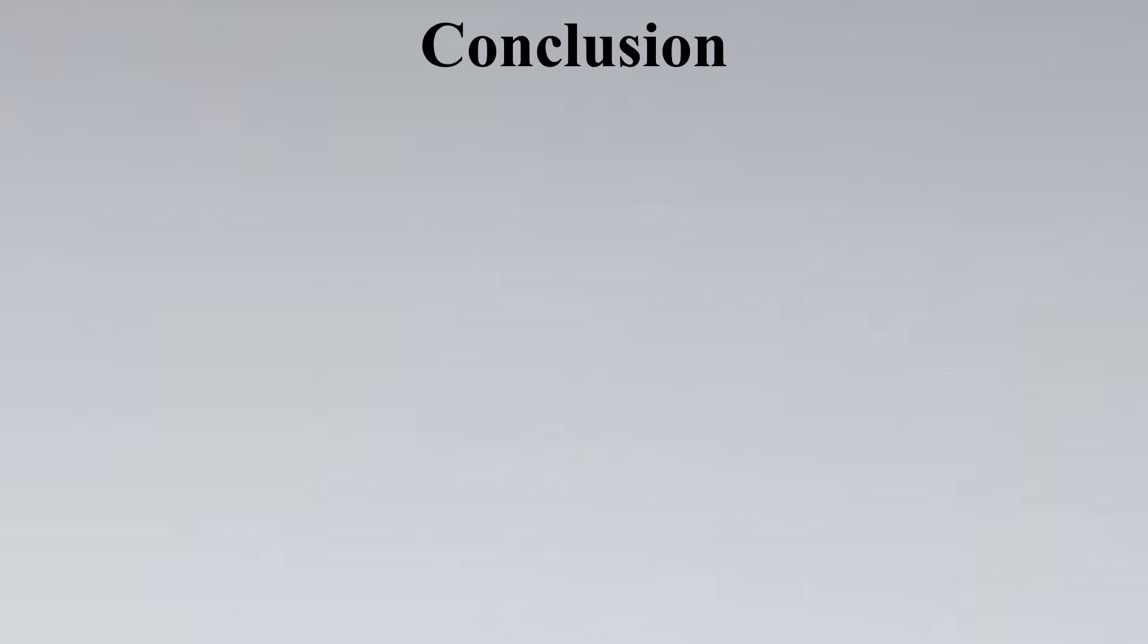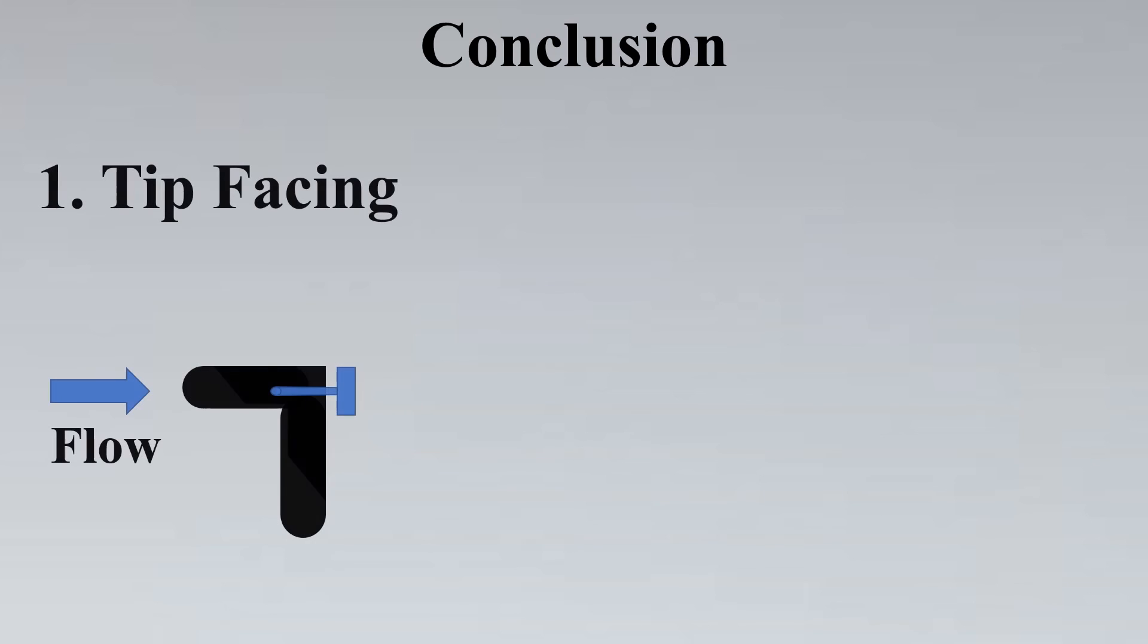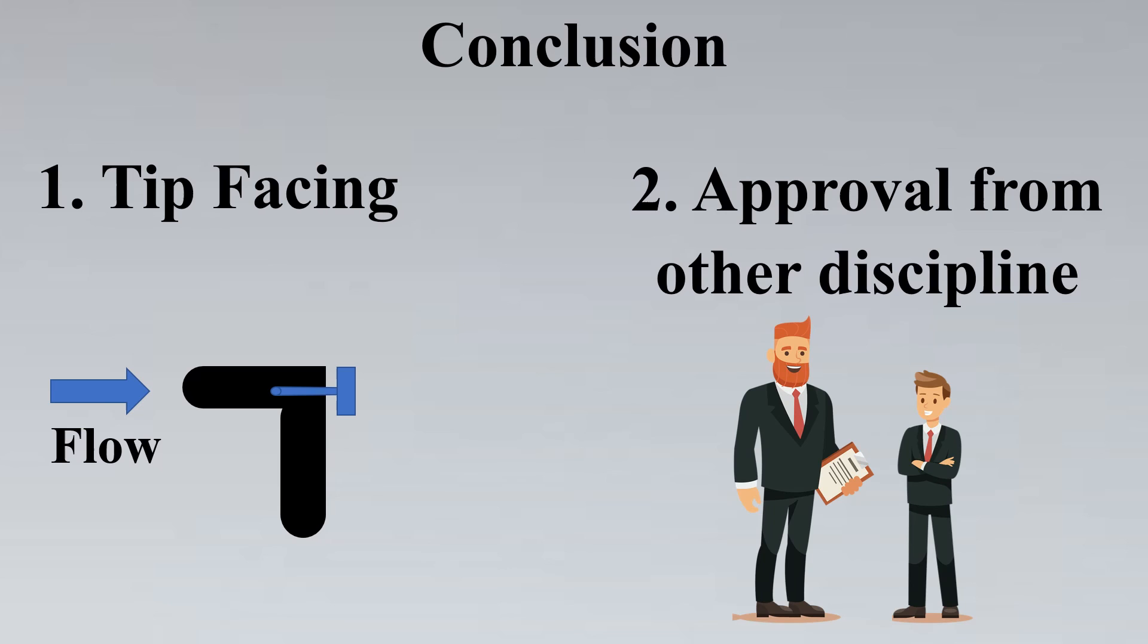Now let's quickly revise the concepts that we have learnt here. The first criteria was the tip facing towards the flow so if the tip is facing towards the flow then we are good to go. So less area is exposed, less chances of vortex and vortices and less chances of the thermowell being exposed to such high vibrations. The second one was approval from other disciplines where we saw that the process had oil and water and we had to measure the temperature of oil. So we had to see exactly where the tapping is possible or feasible for other departments.